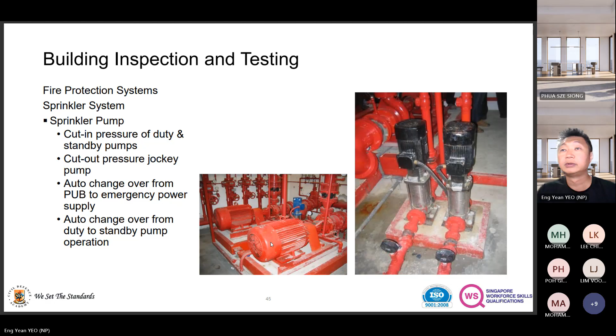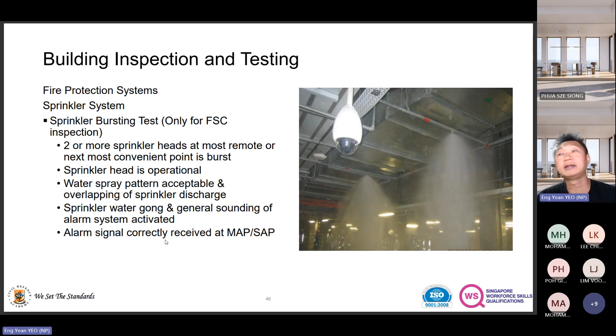Okay, so sprinkler burst, that's for FSC inspection, but usually so far I don't really see them test it. Probably during testing and commissioning before TOP, they'll do it just to make sure it overlaps, that the sprinkler head is operational, the alarm can sound off, and the signal is correctly received. That's why monthly testing is so important, to make sure the alarm panel and the main alarm panel get the correct signal.